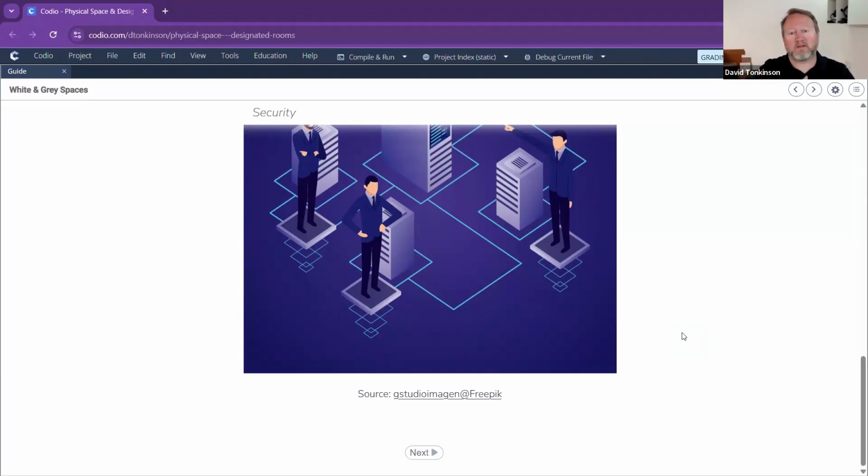I remember at DEMARC, they actually have a really tiny printer system that when you get a ticket, because no one's going to remember all those details, no one's going to remember the serial number. You're not allowed to take a phone in, so you can't snapshot it or read it off of a phone. So they literally had a tiny ticketing system that when you had a job, you said, okay, print that, and it would print a tiny slip of paper that gave you the room, the rack number, and indeed the U that it was on, and the serial number of the device. And you physically carried that round with you and then put it in the bin afterwards. Okay, so you physically take that round.